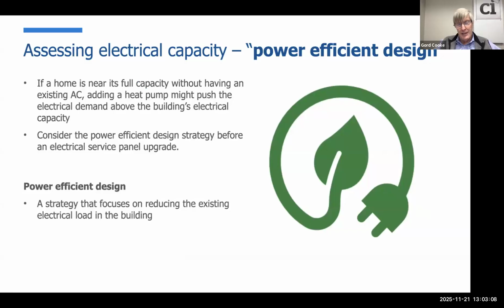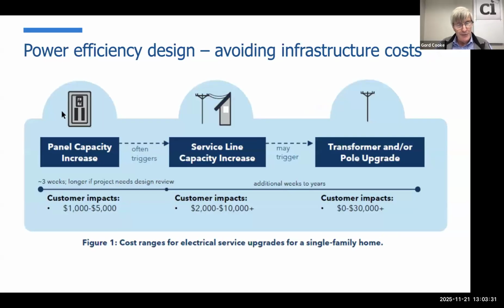In fact, there is a technique or strategy called power efficient design—looking at the important impact of individual loads in houses, and could we find a strategy before we upgrade a panel size, whether in newer or existing houses, to reduce the need to increase the panel size? Because increasing the panel size could be expensive, $1,000 to $5,000 for a homeowner. And what if the line to the house wasn't adequate? What if the transformer on the street wasn't adequate?